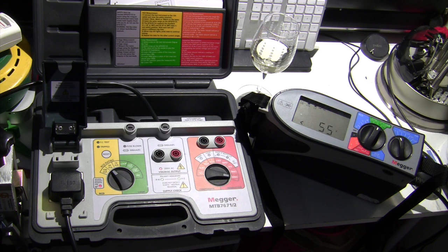Now I will say that I'm expecting a high number here simply because this isn't plugged into where I normally plug it into. It's plugged into an extension lead to get it to where I need it to be by the camera. So we are going to see probably quite a high earth fault loop impedance. Normally I'd get a reading of sort of 0.79, something like that.